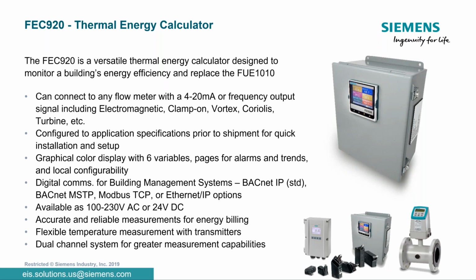It's offered in a dual channel, so it can do either heating and cooling or whatever combination you want to do together. It can be configured with temperature transmitters or RTDs, and can also be configured based on the fluids for the specific heat. So if you're running a chilled water line with 30, 40, or 50% glycol, we can customize that as well to provide the accuracy required, especially if it's a billing application. What's nice is the graphical color display with the 6 variables. You've got a lot of pages that will give you different alarms and trending, and it's got a local configuration.